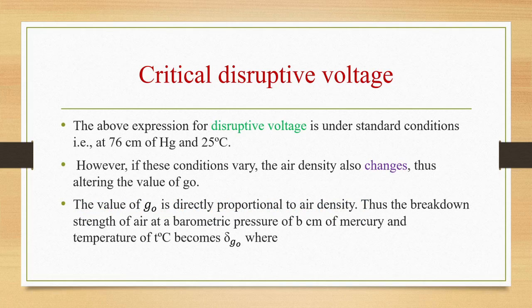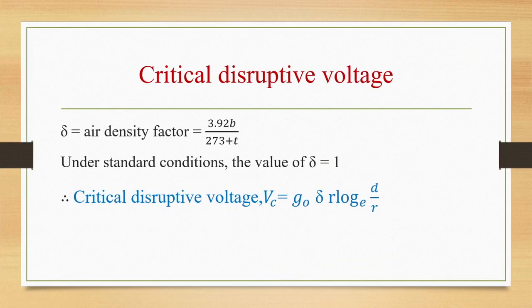The above expression for disruptive voltage is under standard conditions, that is at 76 centimeter of Hg pressure and temperature of 25 degrees centigrade. However, if these conditions vary, air density will also change and the value of g naught will also change. So the value of g naught is directly proportional to air density. The breakdown strength of air at a barometric pressure of b centimeter of mercury and temperature of t degree centigrade will become delta into g naught, where delta is the air density factor, that is 3.92 b by 273 plus t. Under standard conditions, the value of delta is 1. Therefore we can write critical disruptive voltage Vc as g naught delta r log d by r base e.